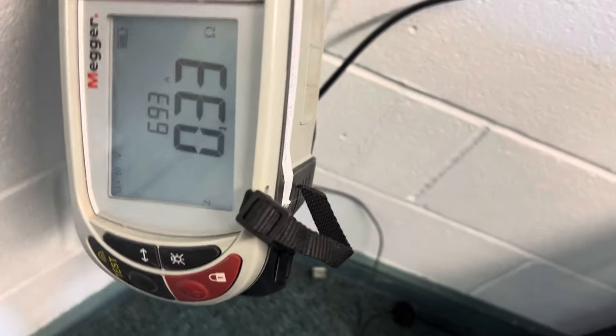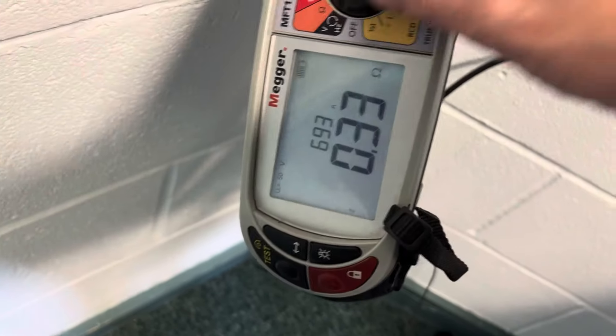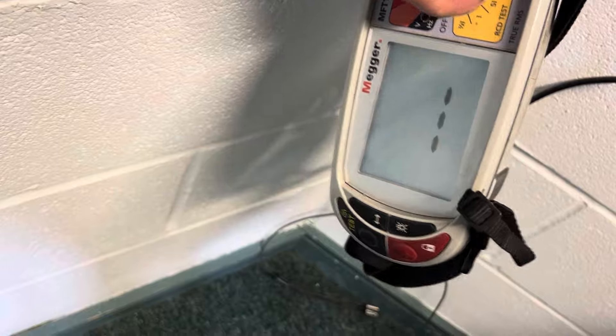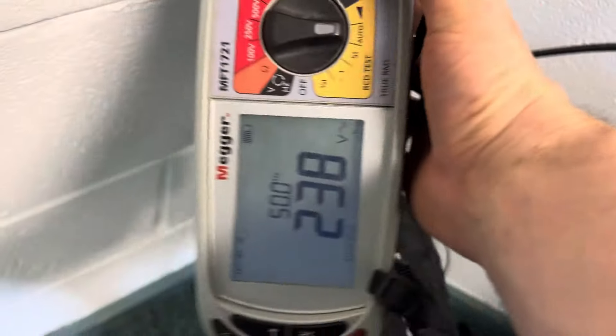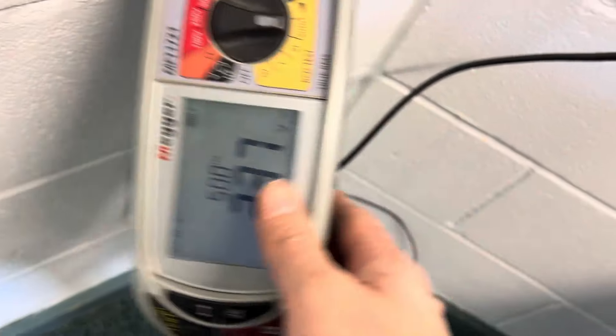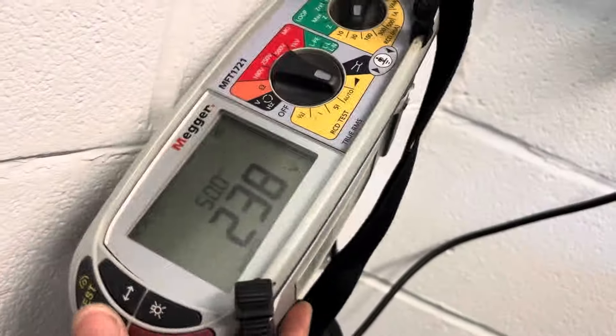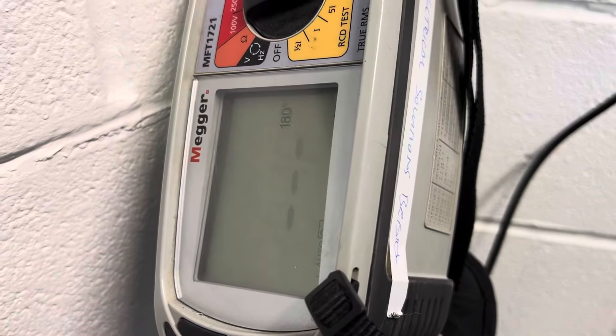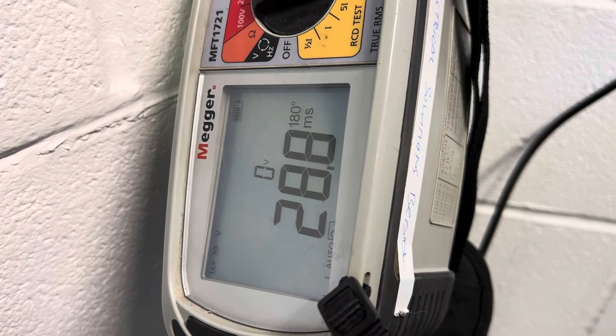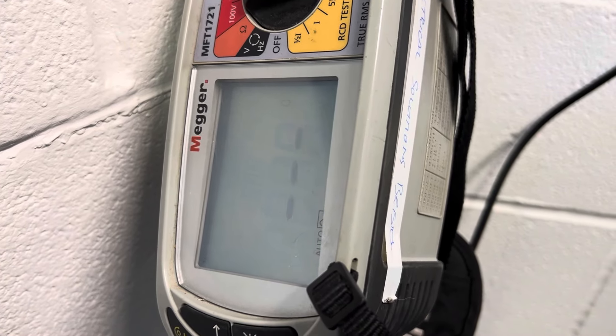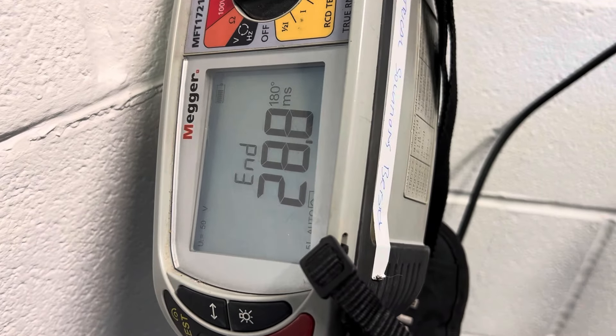So that's our Zs. I'm going to go around and do an auto test. All of the Memshield stuff has always been type A, as long as I can remember, since at least 2006. They've always been type A, but I'm going to test it on the type AC side of it.